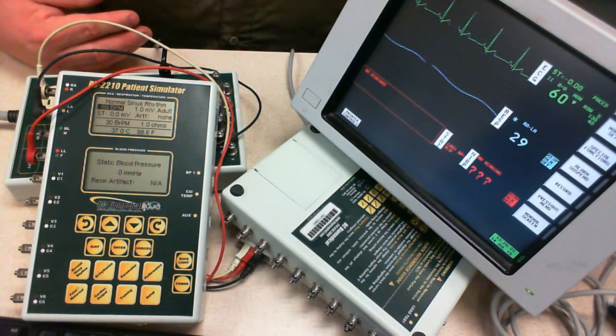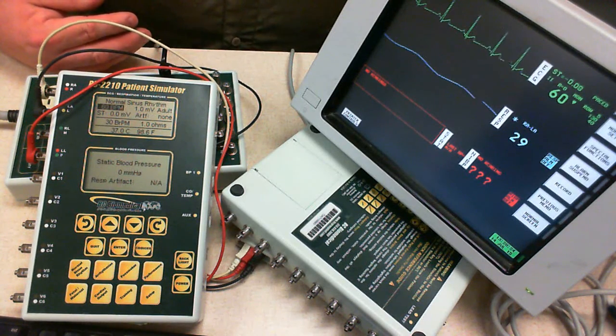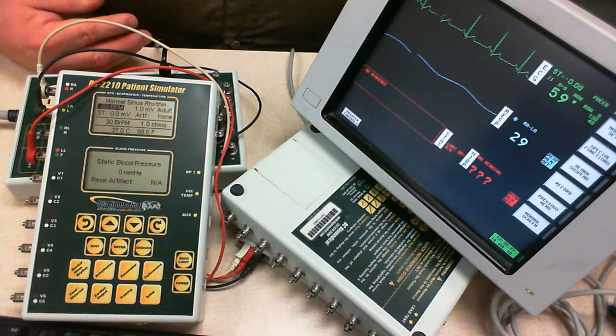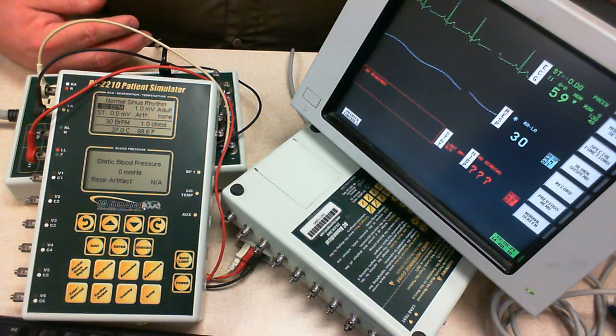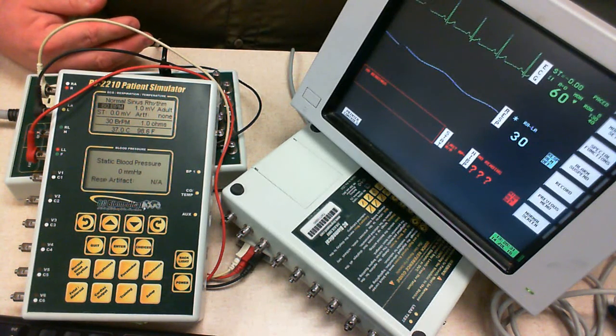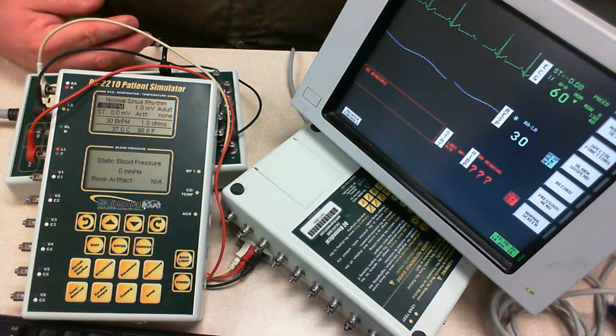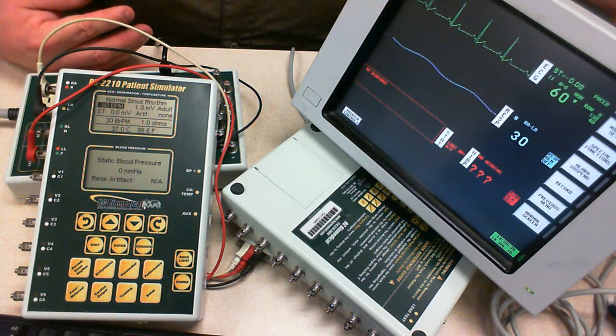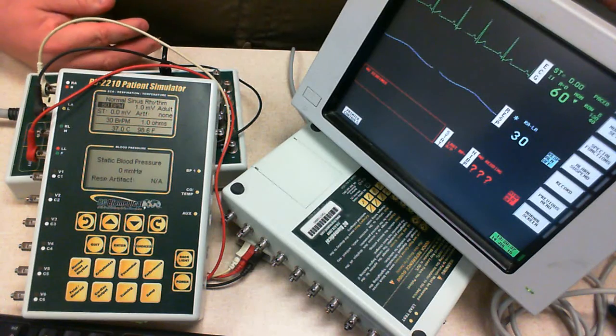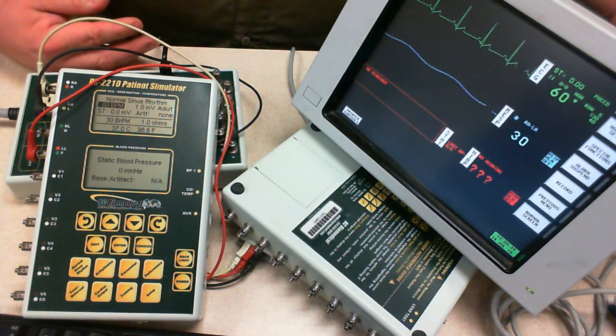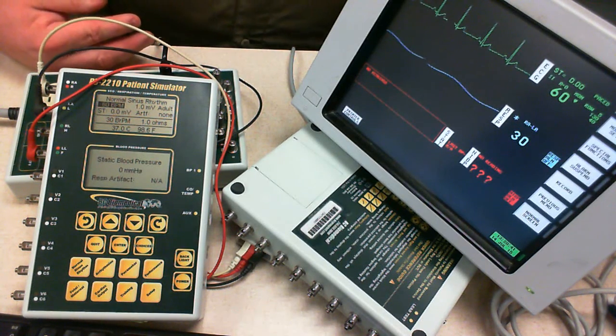We've covered the top portion in electrical safety. Notice that the three new tests are on this sheet for lead to ground, lead to lead, lead isolation. Yes, I do expect you to do that in this lab. Sound good? Then in the second portion here, the ECG, let's go through rate calibration.